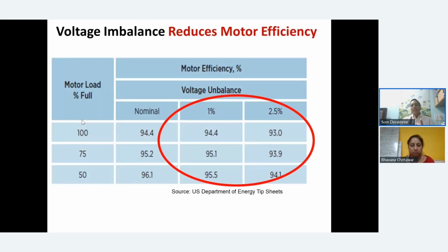Another thing is voltage imbalance. If there is voltage imbalance in the circuit, especially when you have buildings with a lot of single phase loads, you see the motor efficiency fall. If it is 2.5%, there is almost a 1 to 2% fall in the efficiency of the motor. At 50% load it's almost 2% efficiency fall only from voltage imbalance. I have taken this from the Department of Energy.